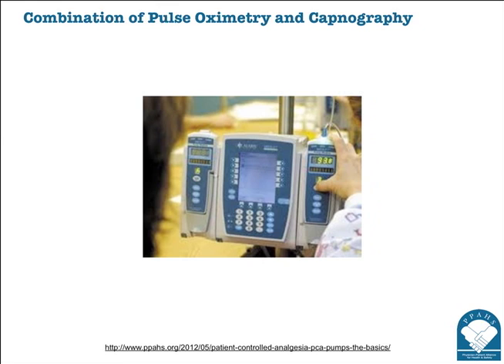They have a built-in algorithm that gives the respiratory therapist or nurse an advantage of knowing that something is starting to happen with the patient because these two parameters aren't matching the way they should, signaling they need to come in and evaluate the patient. Because of that, we can intervene much quicker for patient safety than in the past. So the combination of monitoring both oxygen and ventilatory status is a win-win for the patient.